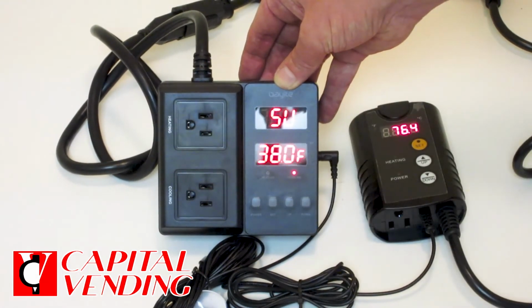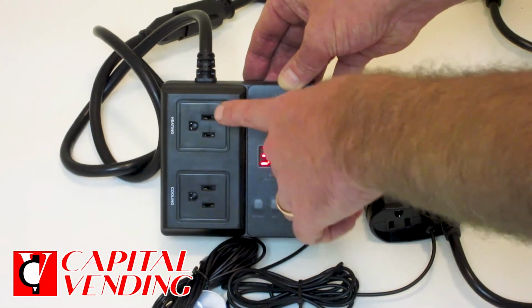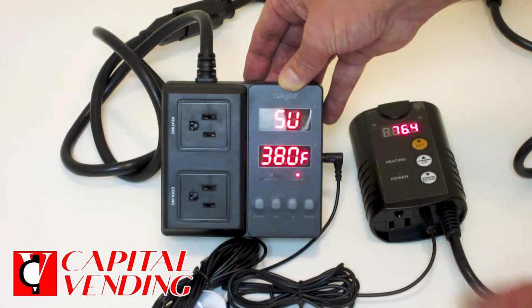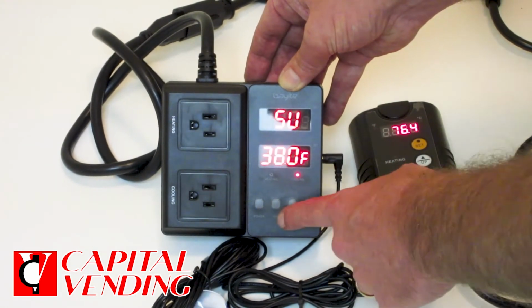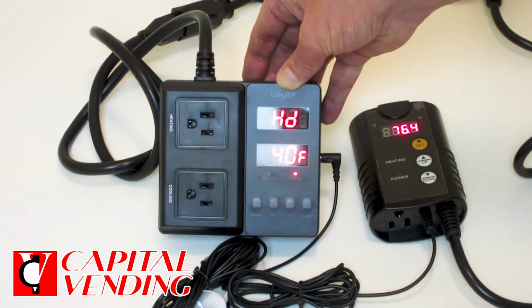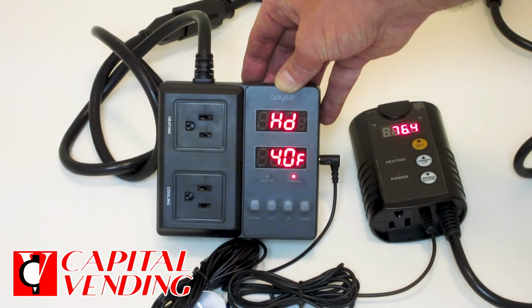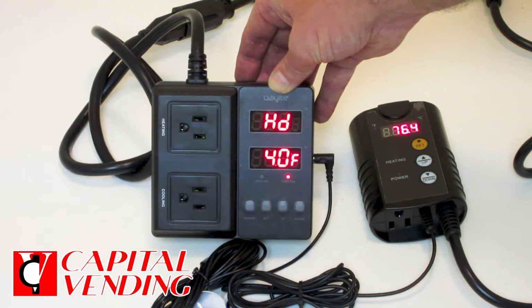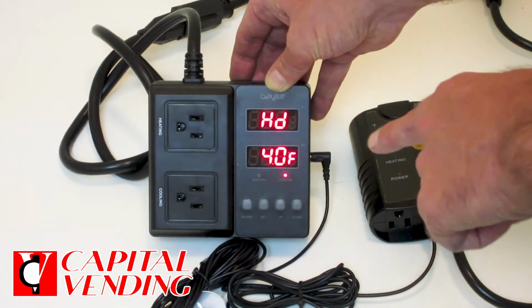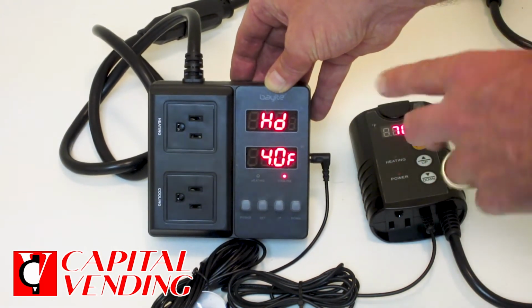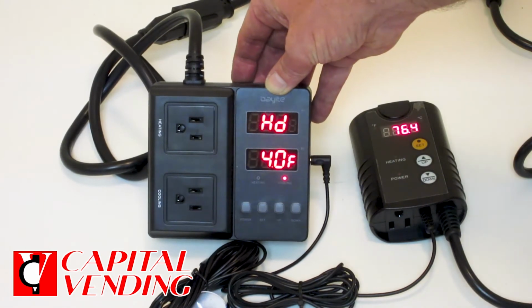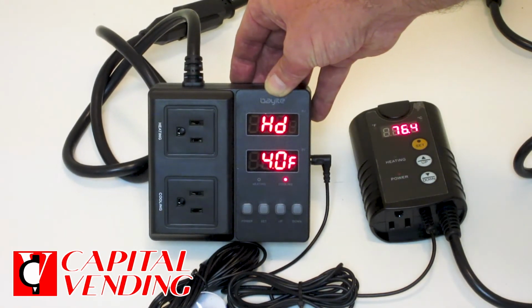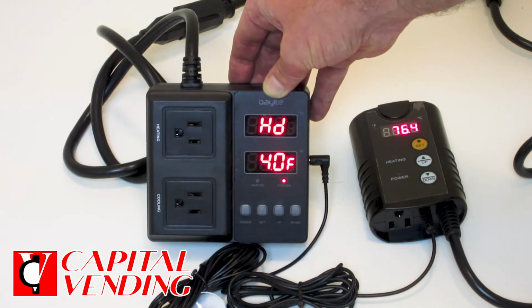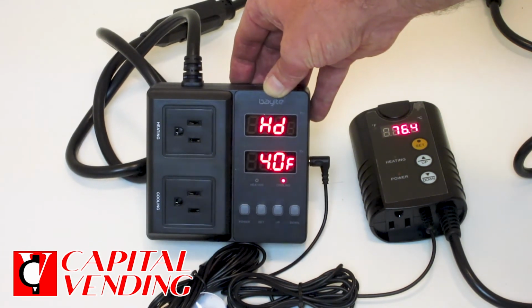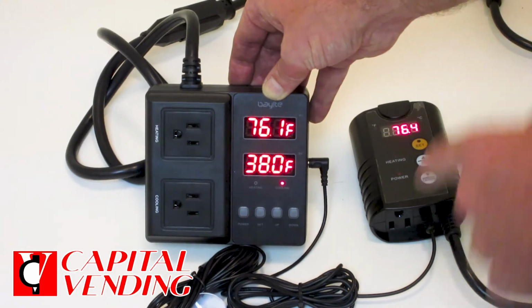And I'm going to talk about the heating and cooling. You don't have to use both. If you're only using this for heating or only for cooling, but if you set it up for both, it works. I'm going to press the set button again. So right now I have my heating differential, which is 4 degrees. Basically this is going to come on when it gets to 34 degrees and heat it to 38. And when it gets to 38 degrees, the heater will go off. So if you want it to be warmer, you need to set that baseline at a higher temperature.